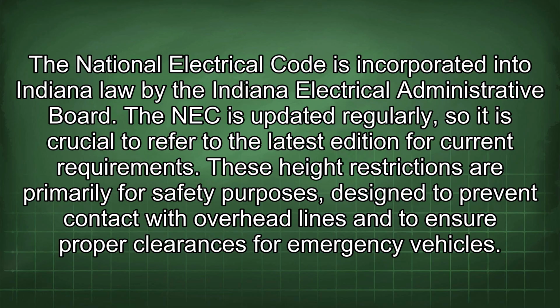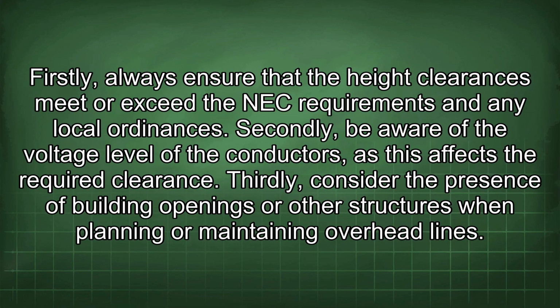These height restrictions are primarily for safety purposes, designed to prevent contact with overhead lines and to ensure proper clearances for emergency vehicles. Firstly, always ensure that the height clearances meet or exceed the NEC requirements and any local ordinances. Secondly, be aware of the voltage level of the conductors, as this affects the required clearance. Thirdly, consider the presence of building openings or other structures when planning or maintaining overhead lines.